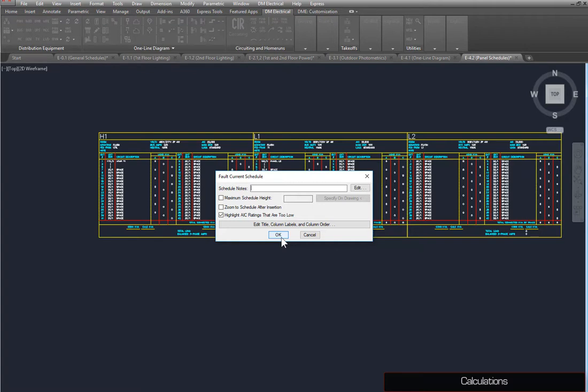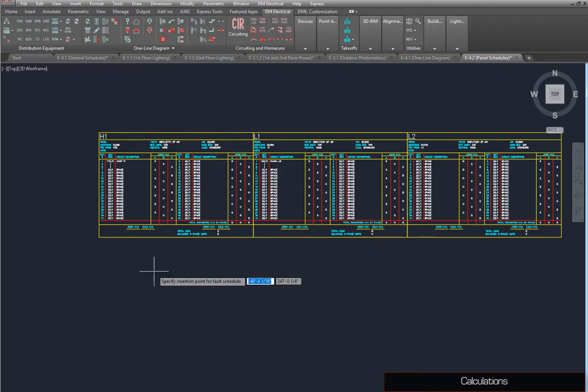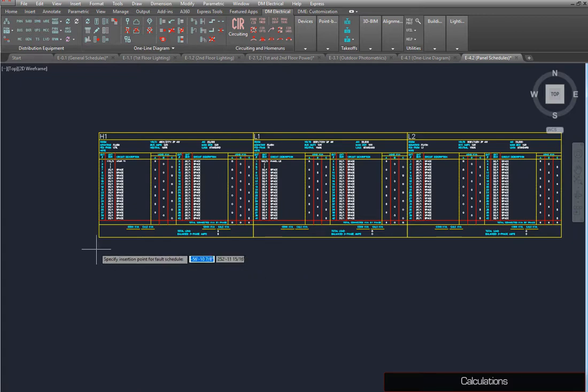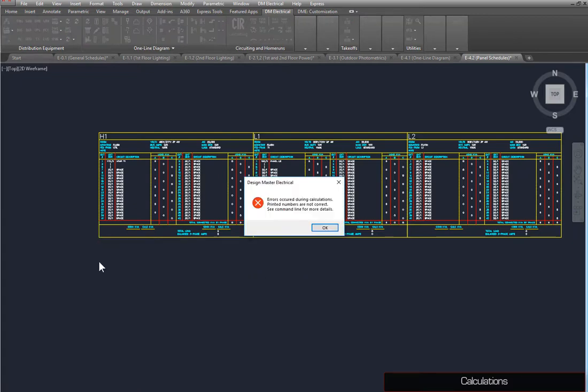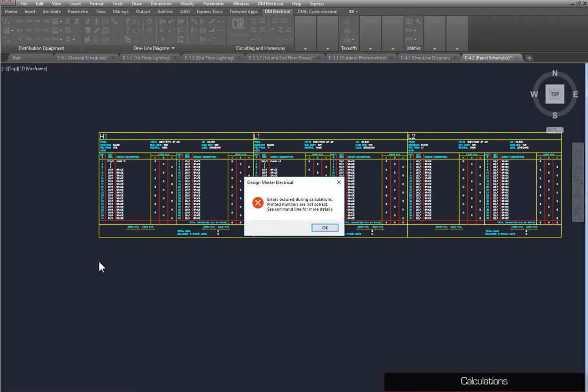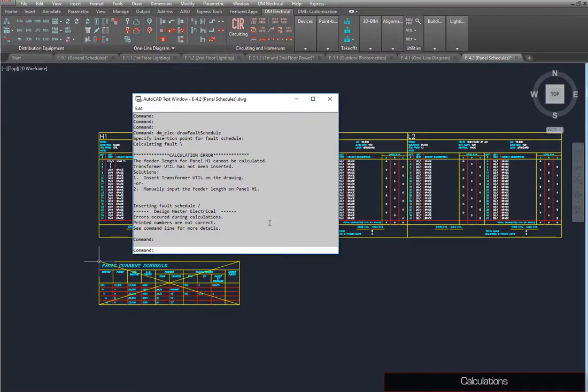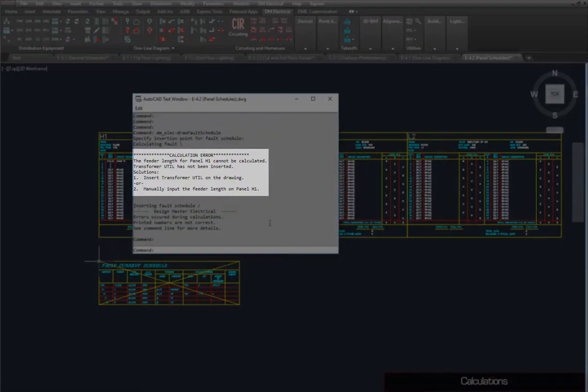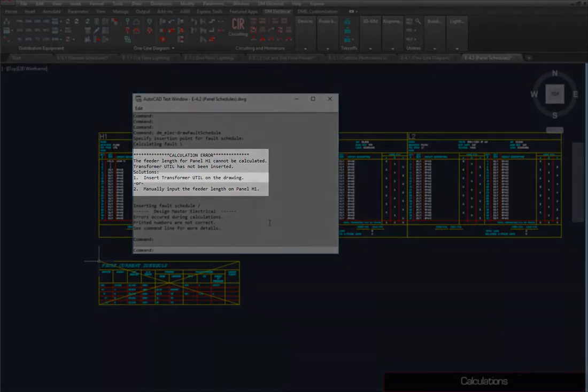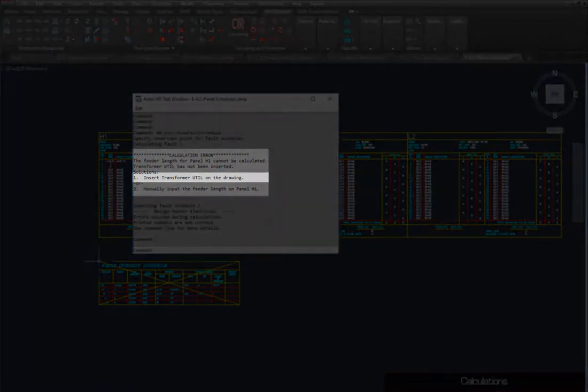Insert the schedule on the drawing the same way you inserted the panel schedules earlier. If you've been following along, you should receive this error message. This will occur whenever additional information is needed to fully run the fault calculation. More information about the error is available at the command line. In this case, the feeder length for H1 cannot be determined. This can be solved by inserting the upstream device on the drawing, or entering a feeder length manually.